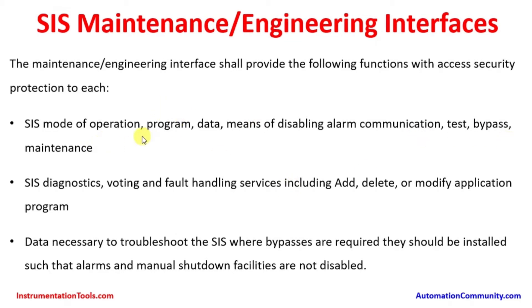All these activities shall be required to be done during plant operation — meaning they are also inline in operation. SIS diagnostics, voting, and fault handling services, including adding, deleting, or modifying the application program. There shall be features to do self-diagnostics on the safety instrumented system, and the program may be required to be modified while the process is in working condition. Where bypasses are required, they should be installed such that alarm and manual shutdown facilities are not disabled, and an alarm shall highlight that the particular system is in bypass.